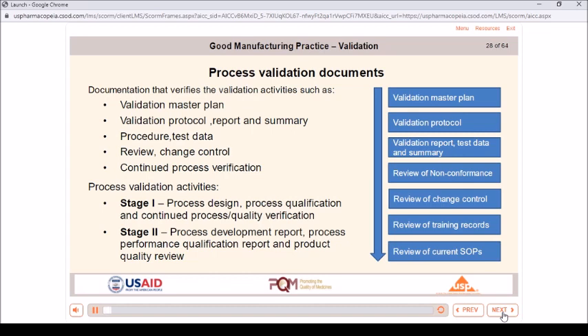Process validation documents. Validation master plan. All validation activities must be described in a validation master plan, which must provide a framework for thorough and consistent validation of product. Key elements of validation are requirements, design control, testing, change control, traceability, and monitoring. Process validation master plans must include: A. Introduction with the scope of the plan, e.g., sites, systems, processes, responsibilities by function. B. Related documents, e.g., risk management plans, products, processes to be validated and or qualified.